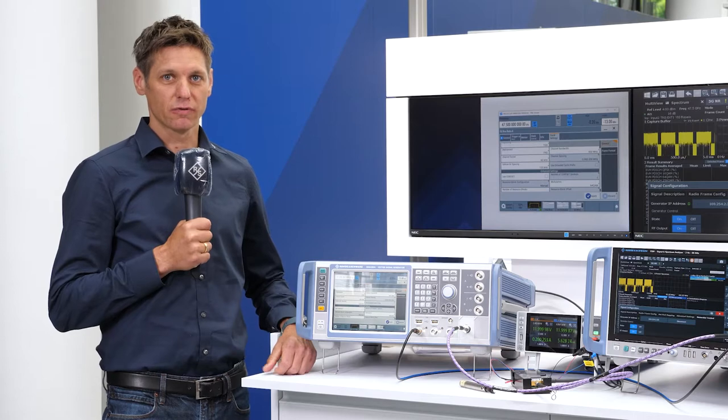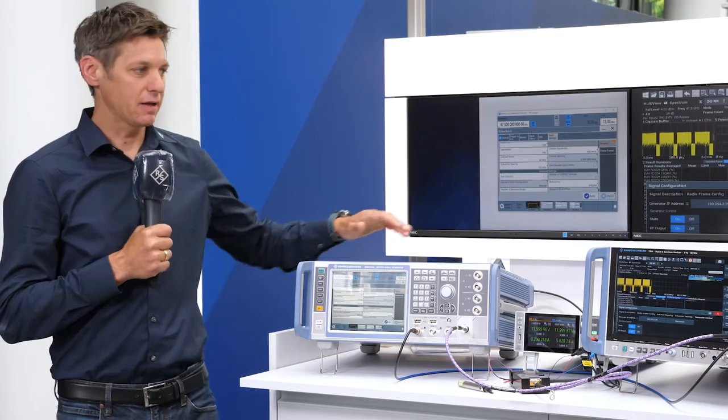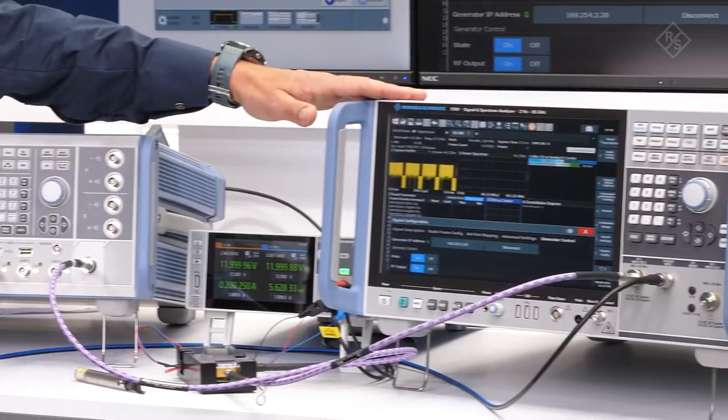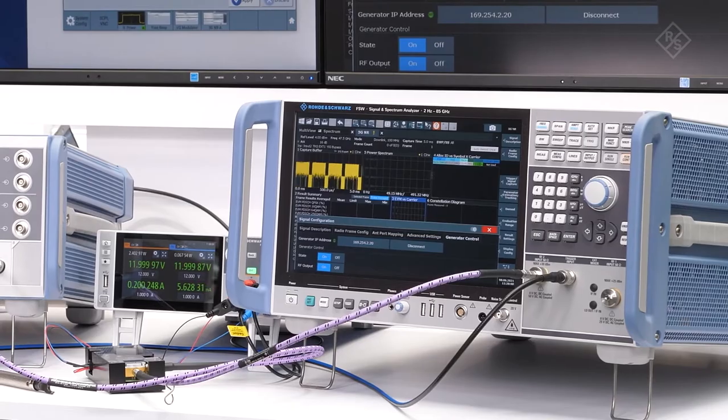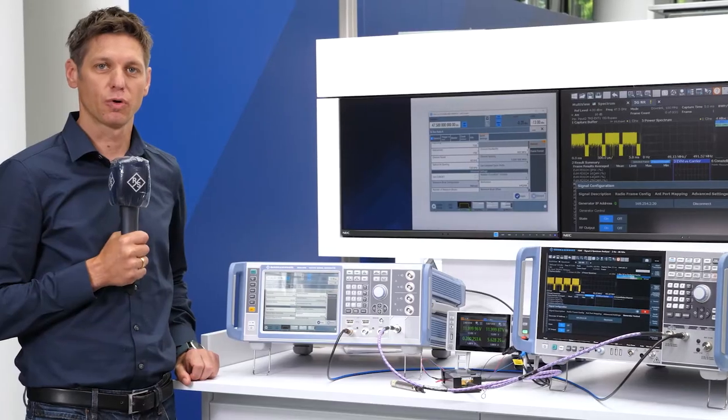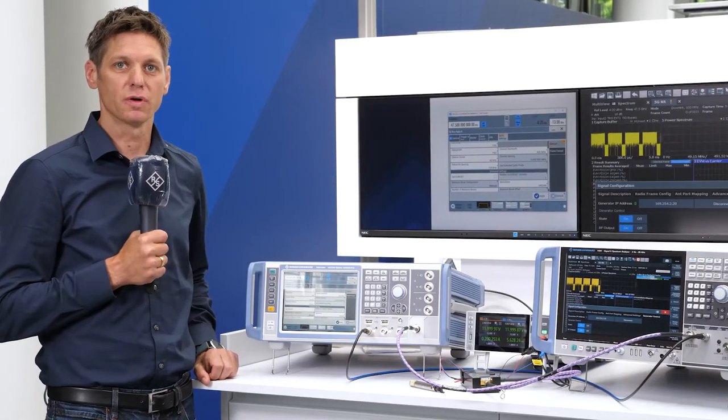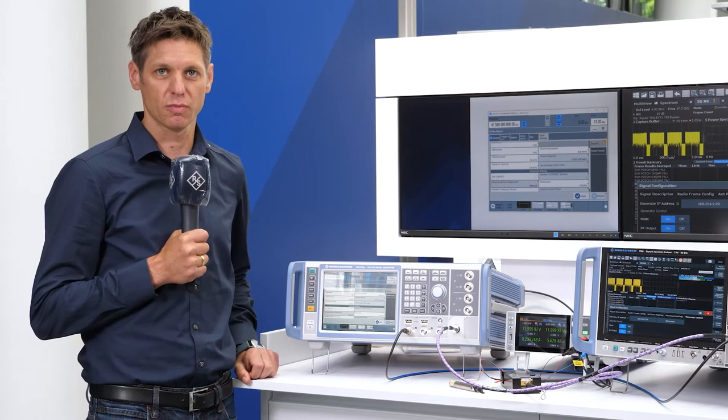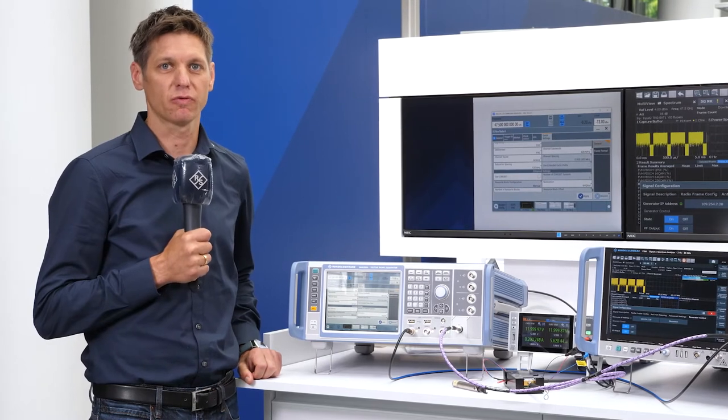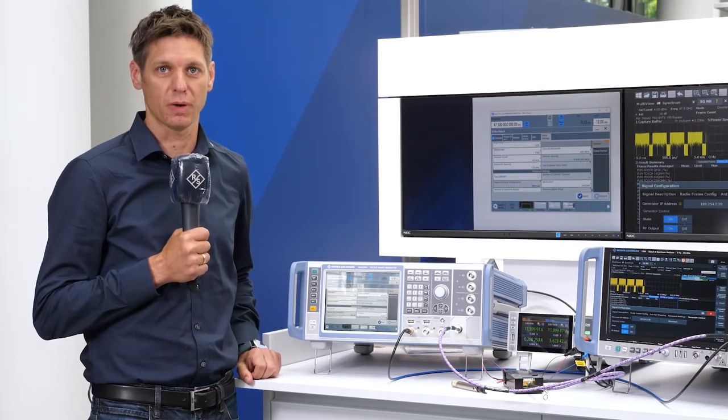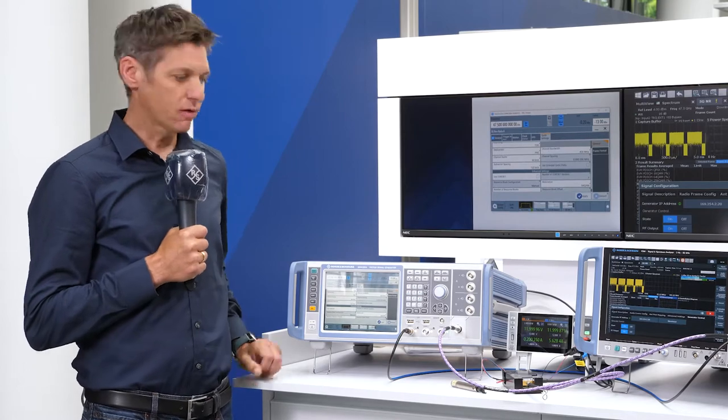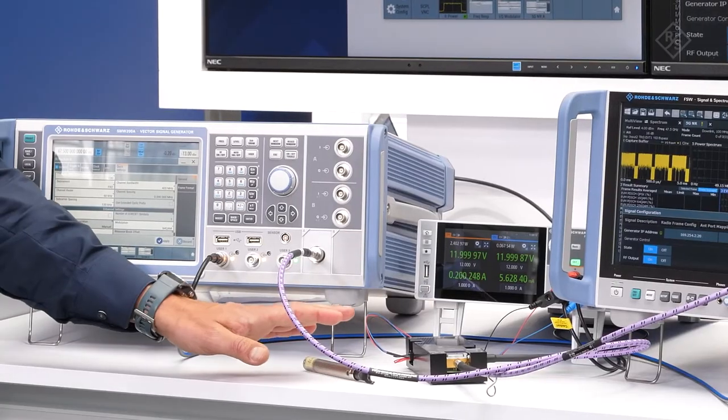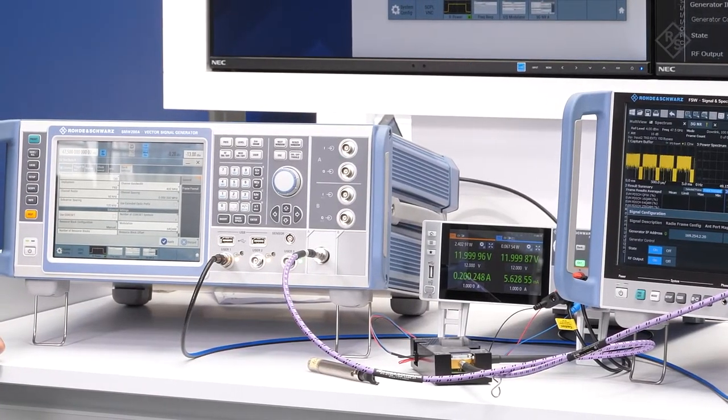The setup consists of the generator and the high-end signal and spectrum analyzer FSW85 which supports up to 90 GHz of image-free spectrum and up to 8.3 GHz of internal analysis bandwidth. As device under test, a commercial power amplifier is used in between.